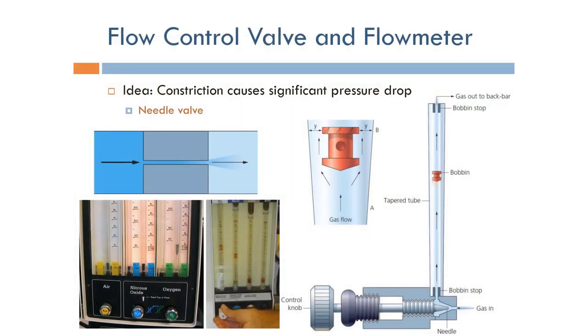The first part that takes care of mixing the oxygen and the nitrous oxide is based on a very simple idea that the constriction causes significant pressure drop. Basically, if you'd like to mix oxygen and nitrous oxide, we can use what's called a needle valve.